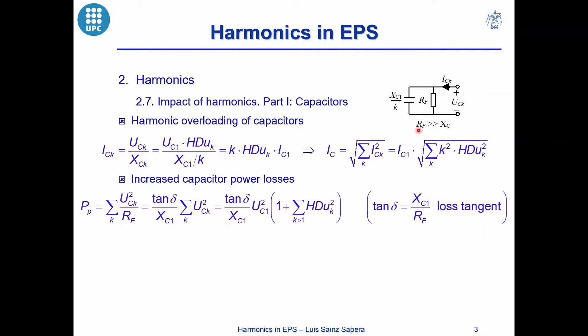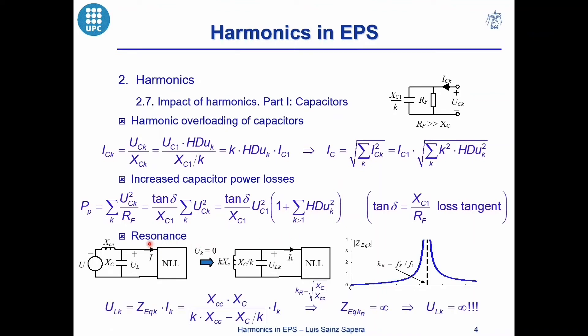The equivalent circuit of a capacitor has a resistance of high value connected in parallel with the capacitor. The losses in this resistance are the sum of the harmonic voltage squared divided by the resistance. By using the loss tangent of the capacitor, we can observe that the losses depend on the harmonic content of the supply voltage. Broadly speaking, the loss tangent is small because the resistance is high, and the losses in a capacitor are also small. The third effect on capacitors related to harmonics is the resonance phenomenon.